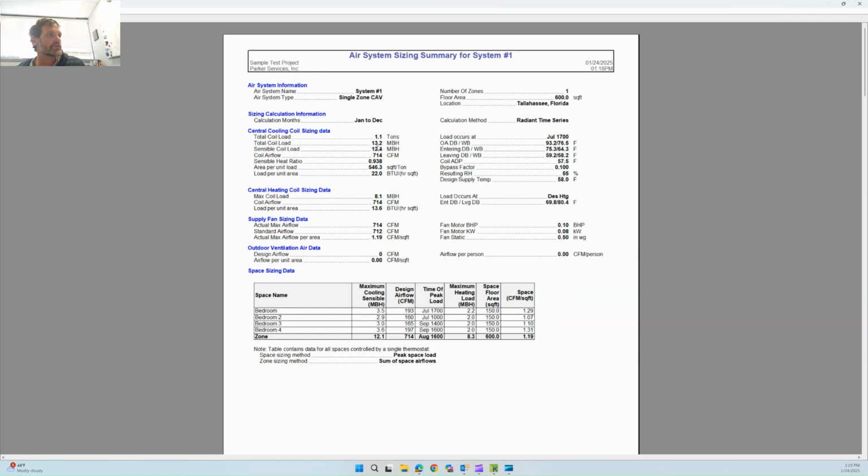1.5 tons is 18,000 BTUs, which is larger than what we're saying we really need, 13,200. But we have 12,400 of sensible load. That's going to be closer to the 1.5 ton to get you that sensible load. We normally are going to size based on the sensible load first. From here, you can create a PDF, you can print, you can go to the next page.